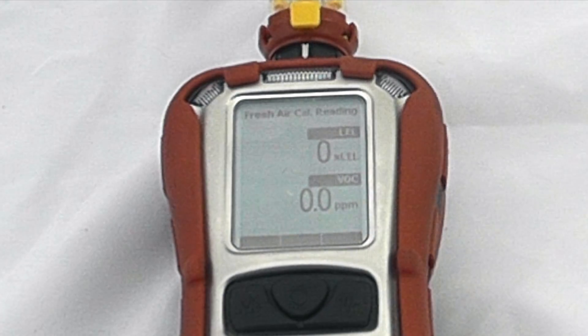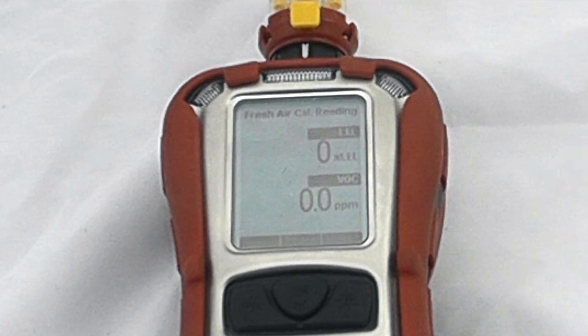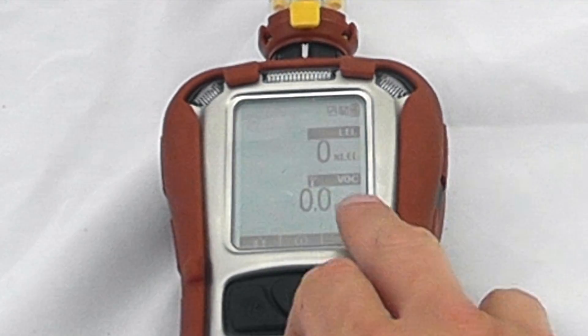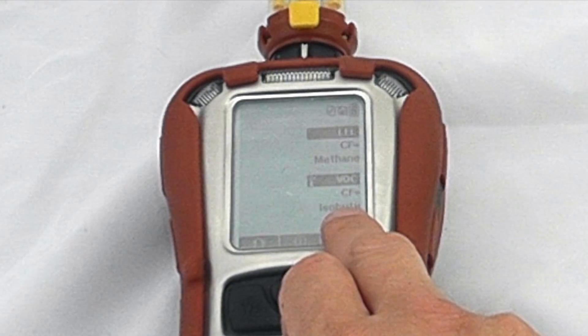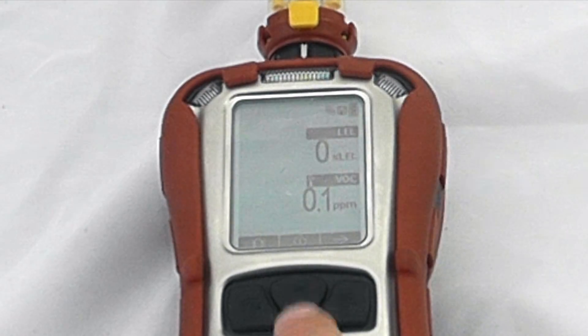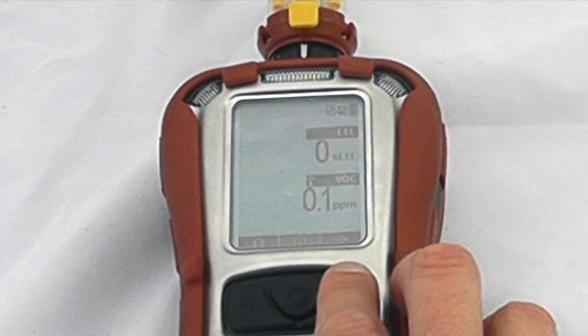The fresh air calibration is reading 0% LEL and 0% VOCs, and then it will go into standard measurement operation. We can see we're now getting a standard reading — VOCs set to isobutylene, so I'm getting a little bit in the background, and our LEL which is set to methane. This will operate normally as per any standard MultiRAE instrument.